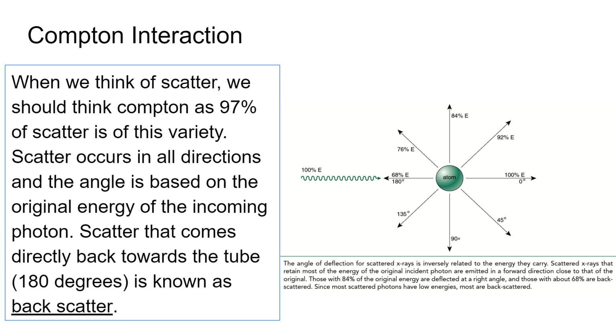You definitely get more energy, though, if you're right in front of the tube. Which is why you should never face the tube at people, except in people you're actually imaging.